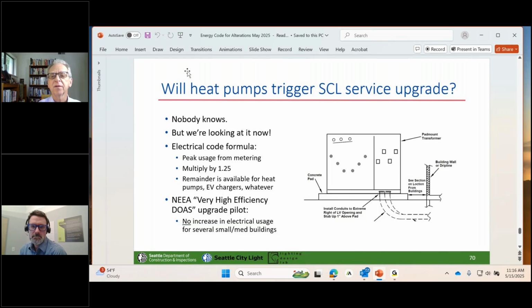The original design is based on longstanding electrical code requirements that typically way oversize systems. For existing buildings, you can simply monitor your electric usage for a period of time and add 25% to the peak load, and any capacity above that is available for heat pumps or EV chargers or whatever you need. So it might very well be that your building can handle this if you do that monitoring and test for it.